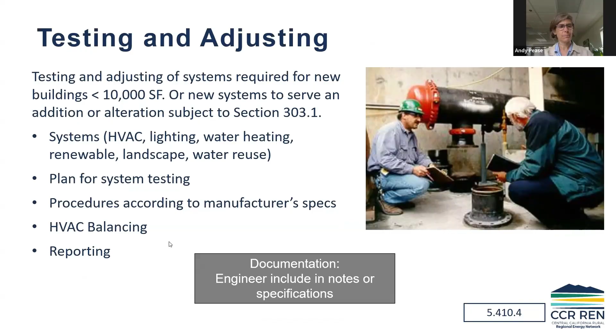Back to CALGreen - if the system is under 10,000 square feet, it's testing and adjusting, and it does require a plan in order to do that, often developed by the engineer in the first place. So make sure that plan is included in notes or specifications.